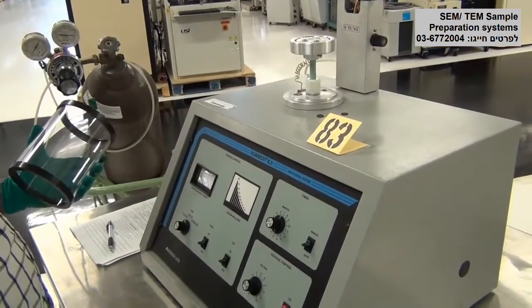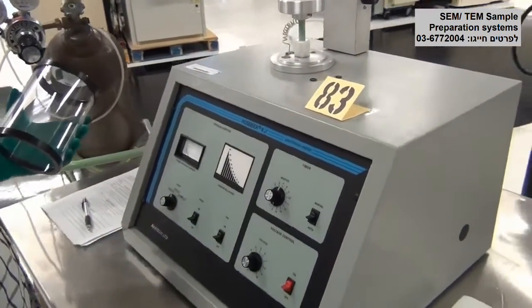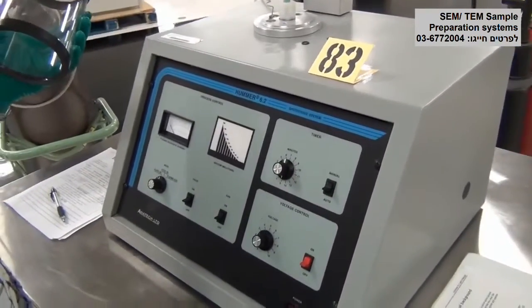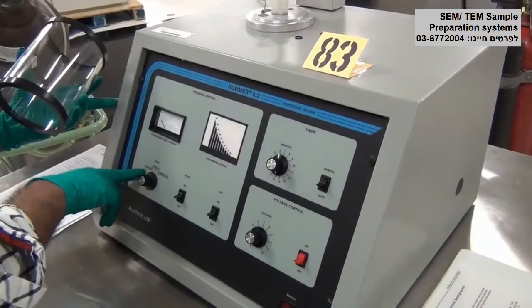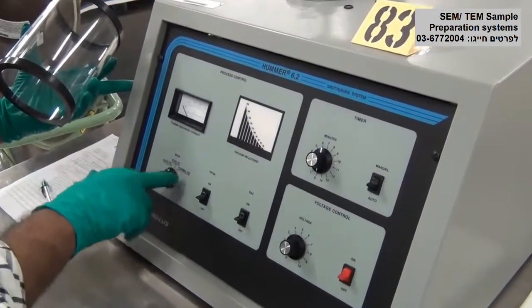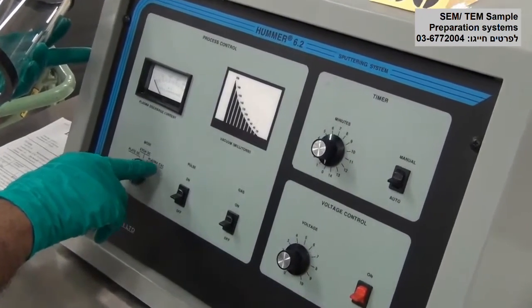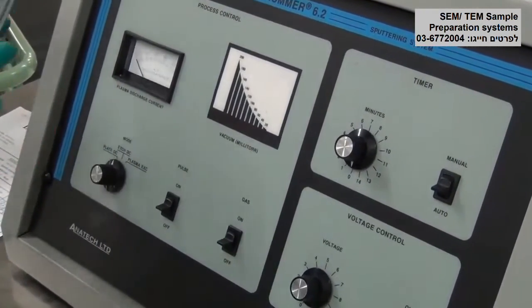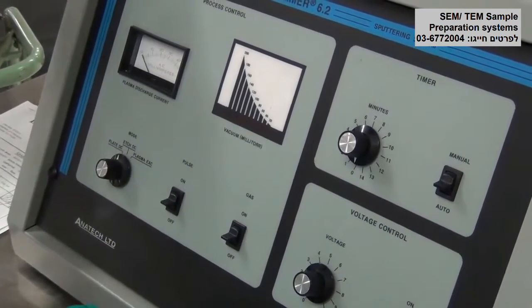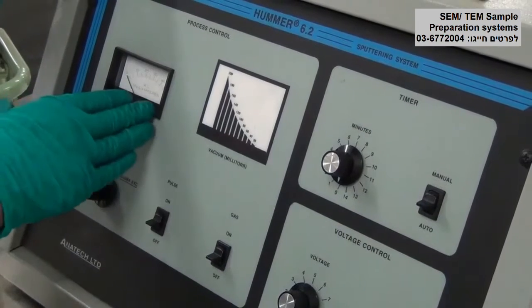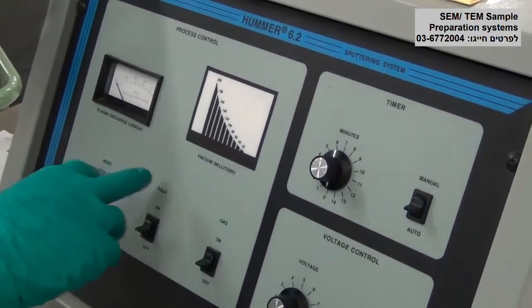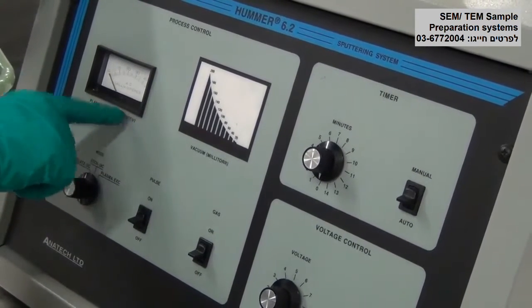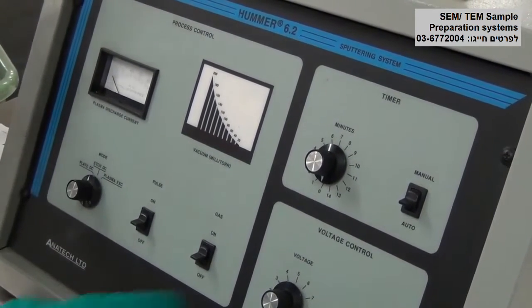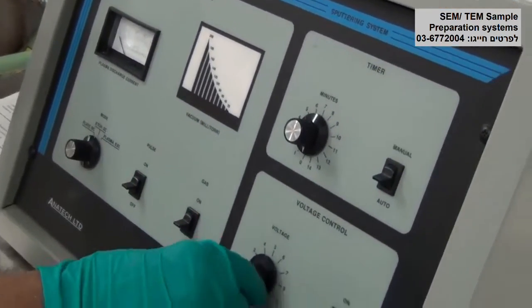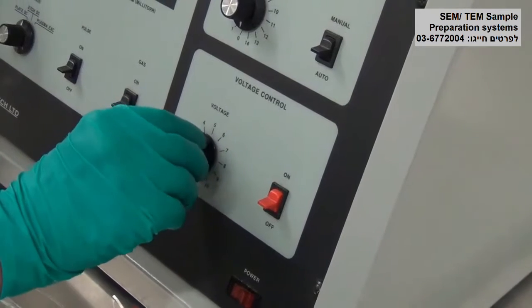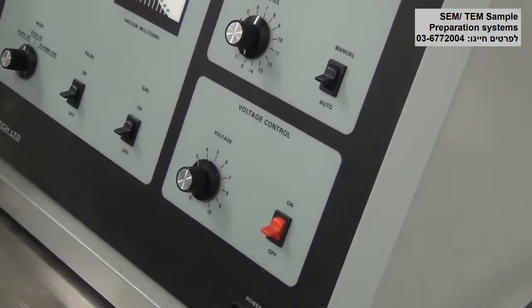Hummer 6.2 sputtering system made by Anatech Limited. This system can do DC plating and DC etching, and also plasma switch mode plating. The system consists of a built-in vacuum pump, and there's a vacuum gauge to indicate the vacuum level, and there's a current, discharge current, plasma current meter, and the system has a timer and voltage control section with voltage regulator and switching on.